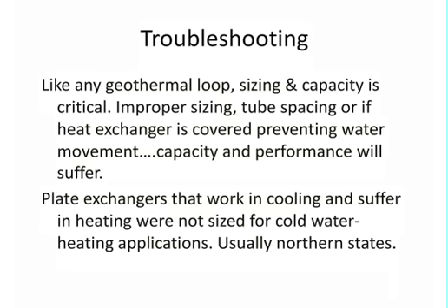Improper sizing and/or tube spacing, if the heat exchanger is covered, preventing water movement, well, your capacity and performance will suffer, I promise you. Again, if you don't allow for the water movement, if you're using the HDPE coils to circulate around all that heat exchange area, well, you don't have enough heat exchange and you could be in problems, heating and/or cooling. You just need to make sure that you're applying it correctly.